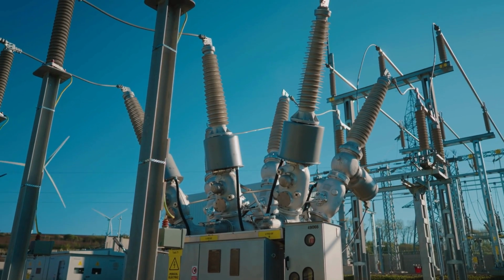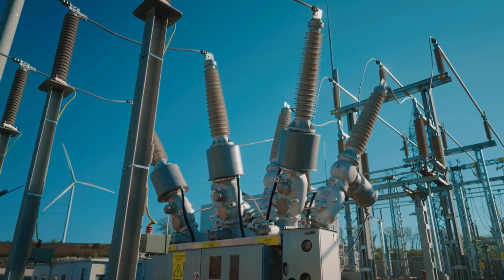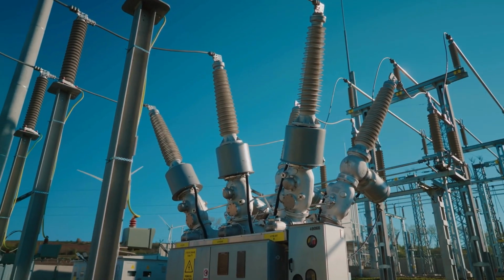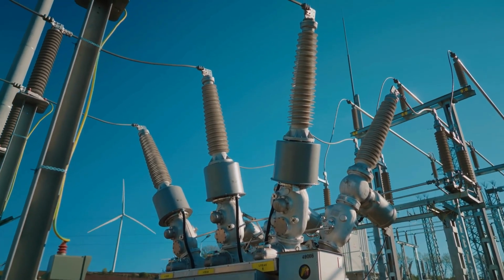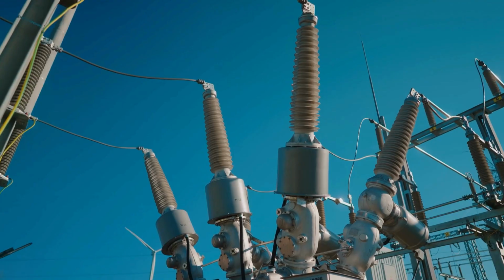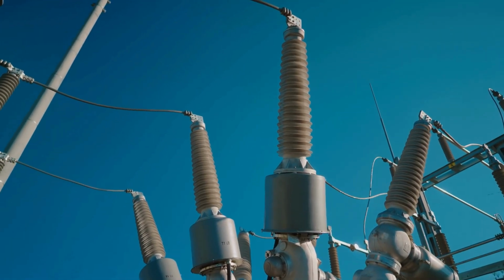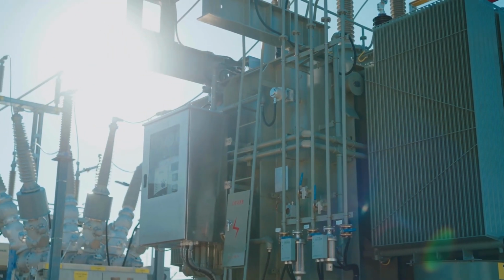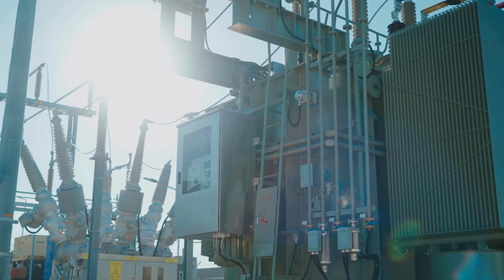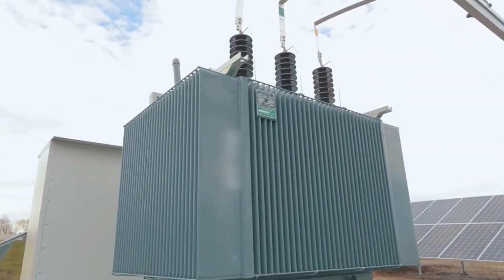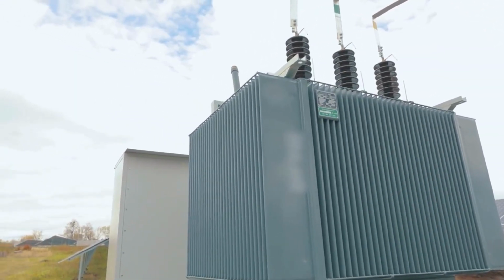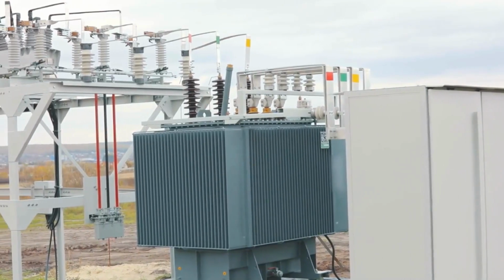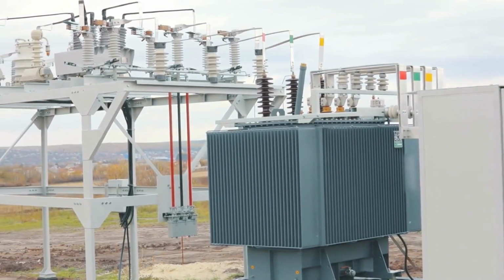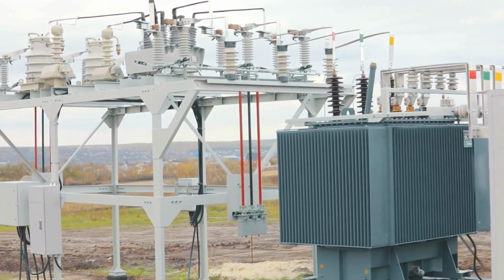5 miles from your house, electricity encounters a substation. The transmission line connects to bus bars, massive aluminum rails that split power like a river delta. These substations reroute power during outages, condition the waves with capacitor banks, and step voltage down for neighborhoods. The transformers here bathe in tens of thousands of gallons of mineral oil, circulating constantly to carry heat away. On hot days, fans blow across radiator fins. On extreme days, sprinkler systems activate. The transformer runs cooler, buying the grid another few hours.